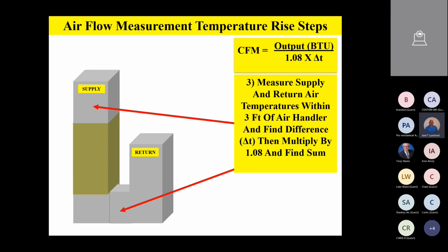So measure your supply and return air temperature within about 3 feet of the air handler, and then find the difference. That's the delta T portion. Find the difference between supply and return air temperature, and then multiply that difference by 1.08. So let's say the supply air temperature is 120 degrees and the return air temperature is 70 degrees. The difference would be 50 times 1.08, whatever that is. And that would be the bottom portion of the formula.